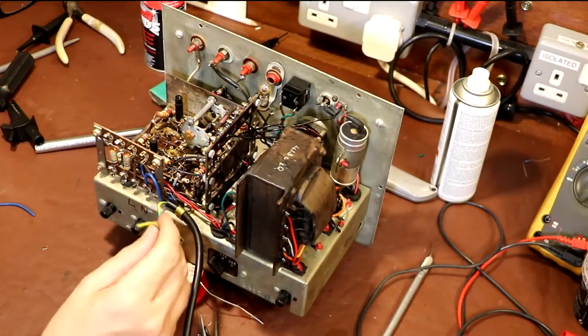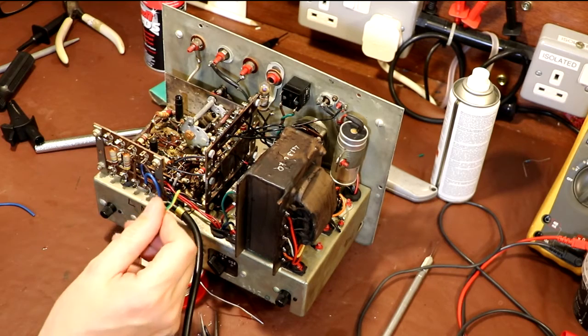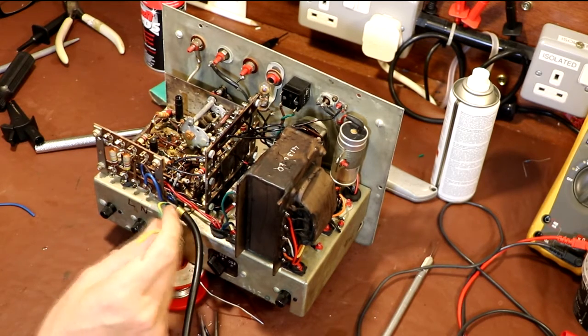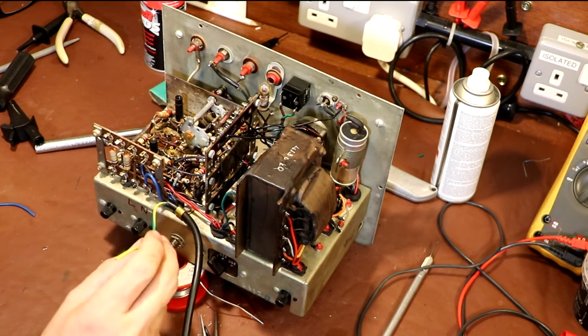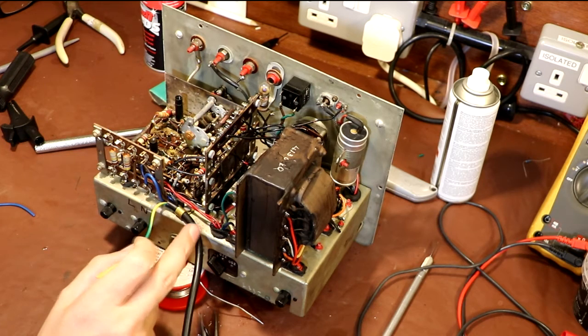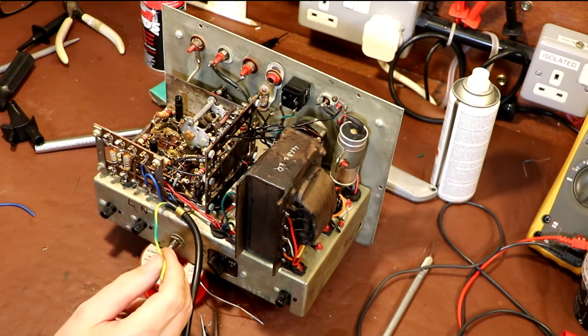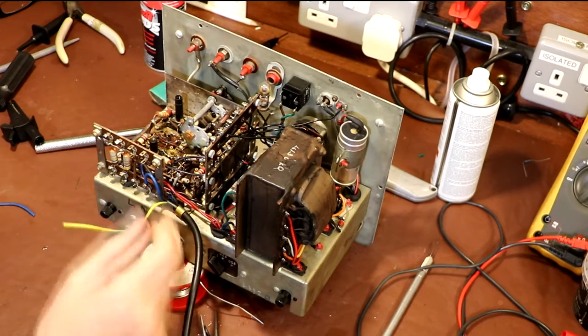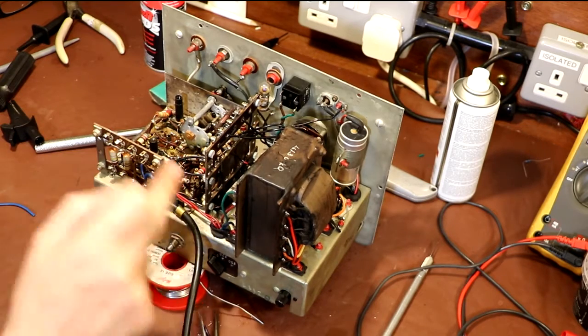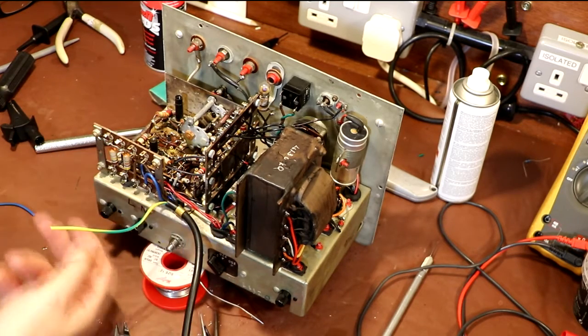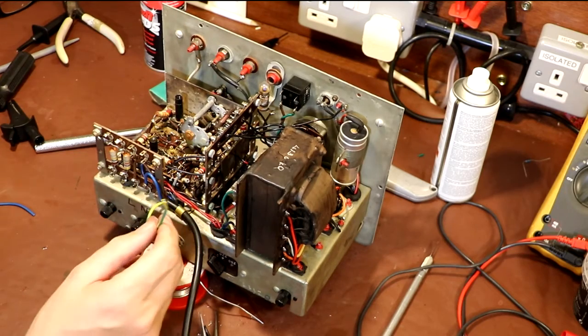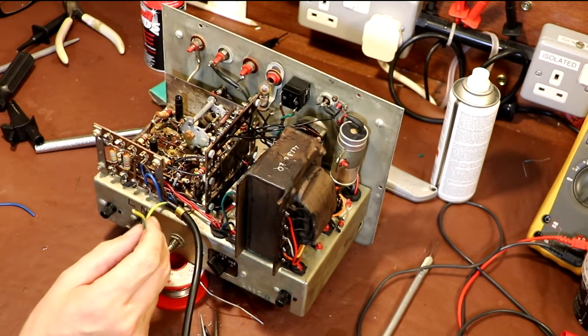So you can see here that I'm fitting a 3-core cable, so we've got an earth wire, and I've got to actually fit this earth wire to some fixing on the chassis. Now the correct way to do it is to drill a new hole so that you use a unique fastening for the earth lead. You shouldn't really use something like a bracket, because somebody can remove the screw from the back bracket and suddenly your piece of equipment has been left unearthed.